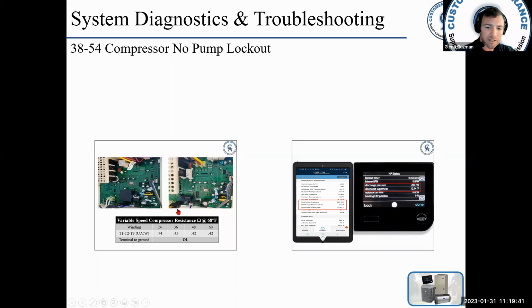What could cause it? Maybe an issue with the compressor. Could be an issue with the transducers. I've seen that happen. You get a compressor no pump lockout and you're saying, hey, that doesn't make sense. You start digging into it and guess what? The unit came on, it started to run, the differential was not met, and then it gives you a compressor no pump lockout. But when you're looking at your gauges physically connected, you had differential. It's just the system did not see it. Okay.